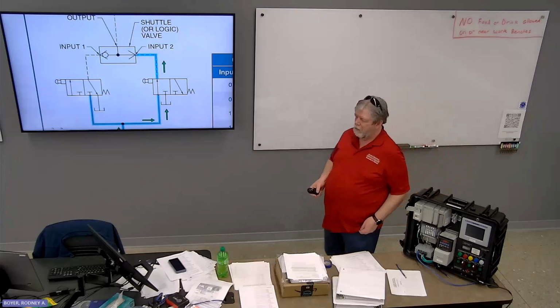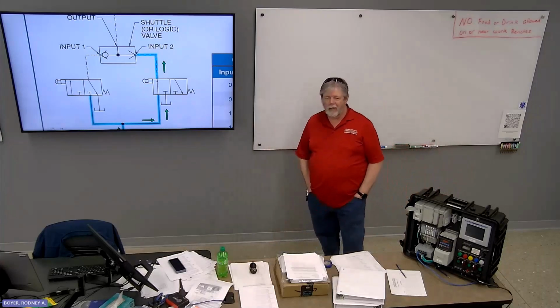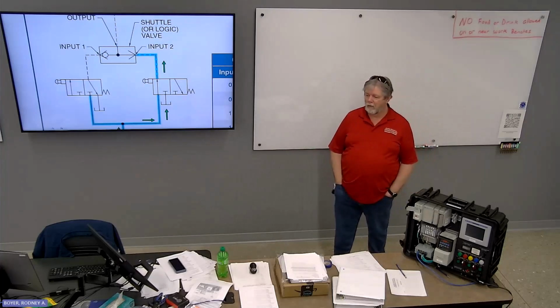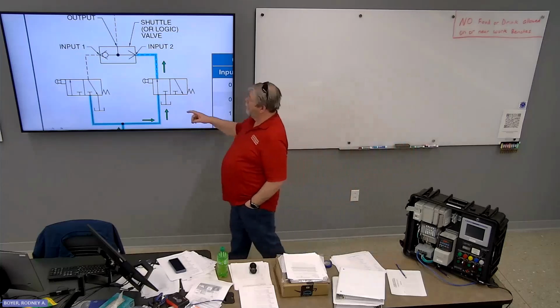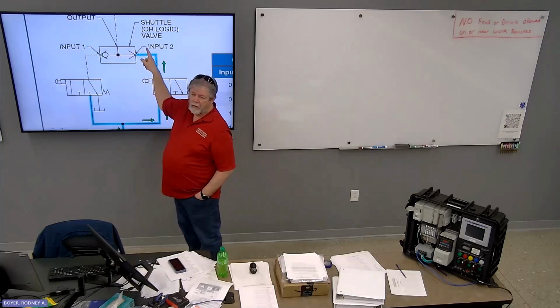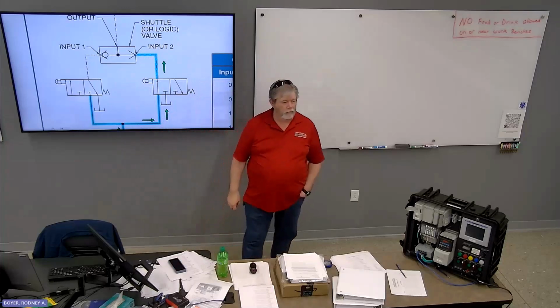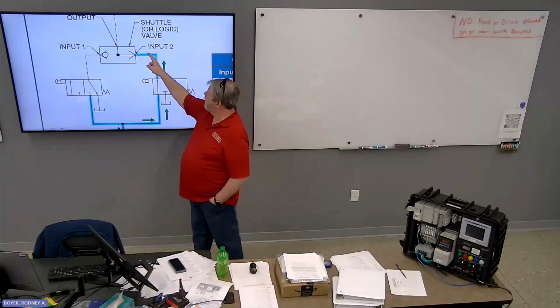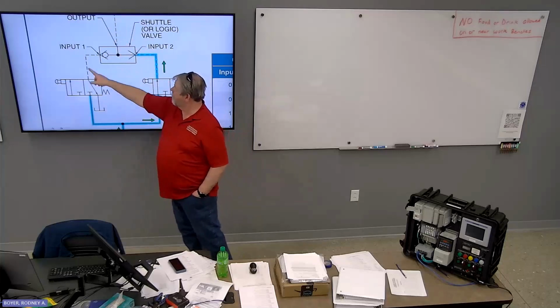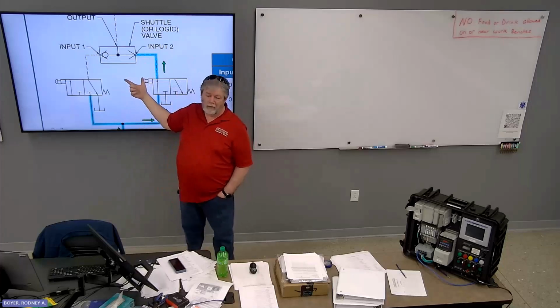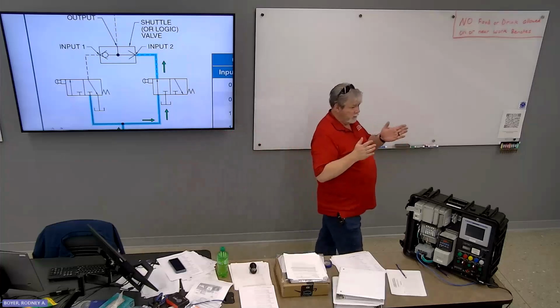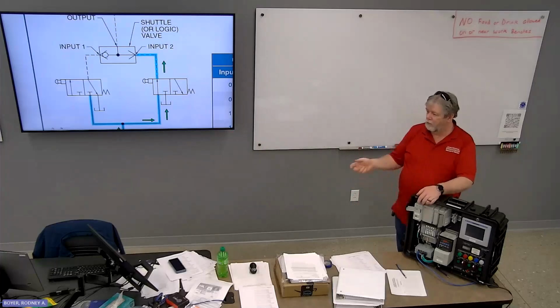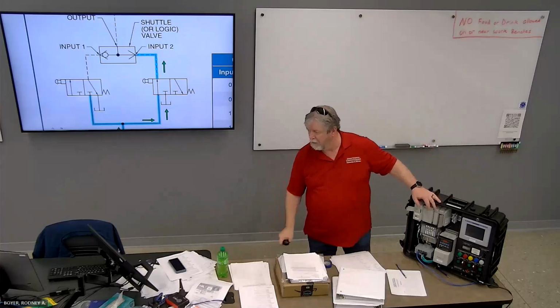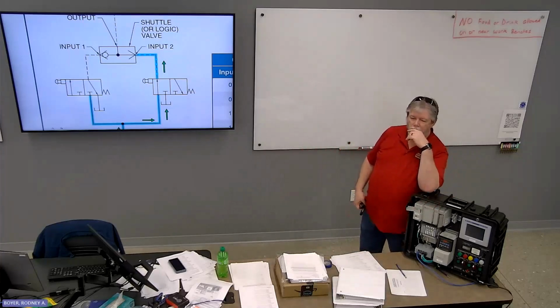On that shuttle valve, notice that one way it's drawn like a check and the other way is drawn like an open check. That's because that's what it is, only that check ball is free to move either way. So if you have pressure applied here, it's going to go that way, through to your output. If you have pressure applied here, it's going to go that way, through your output. If you have pressure applied on both of them, it may not center, but both sides will be open. So flow can go through either one or both of them and still make it to the output. So in this case, it's a regular or, where it could be either one or both. Yep.